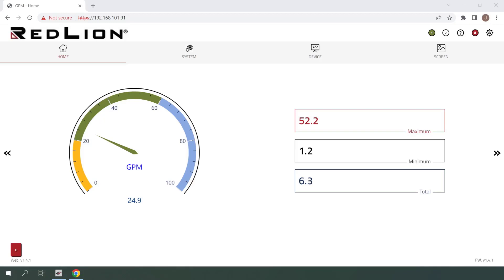For demonstration purposes, my PM50 already has a latching alarm configured which will be activated when a flow of more than 50 gallons per minute is detected. We'll be configuring our user input as the reset for this alarm. We're currently under the 50 GPM setpoint, so I'll now increase the flow to trigger the alarm.